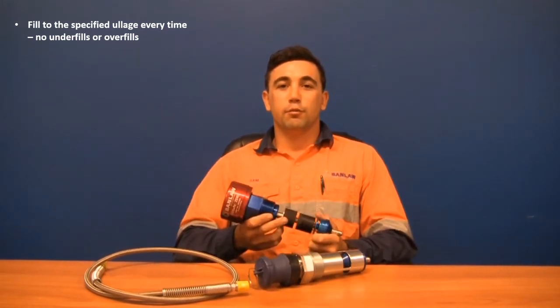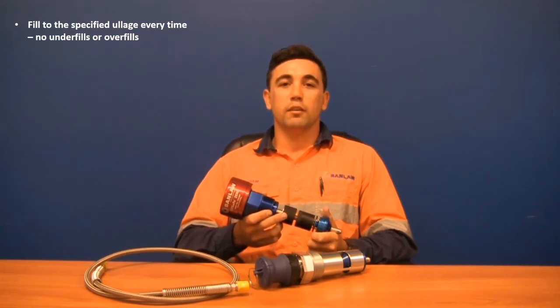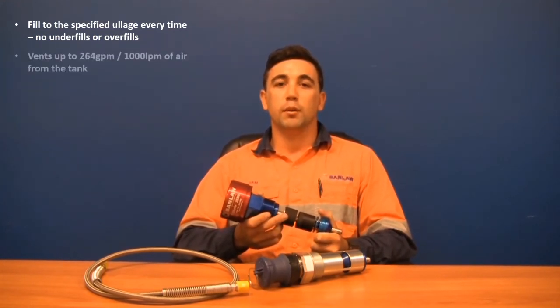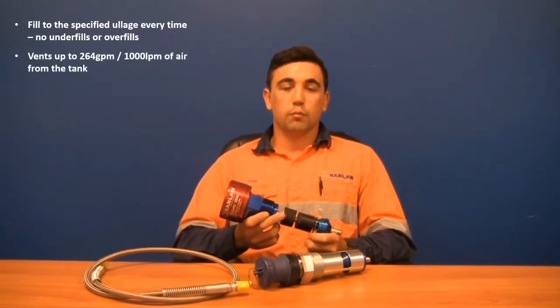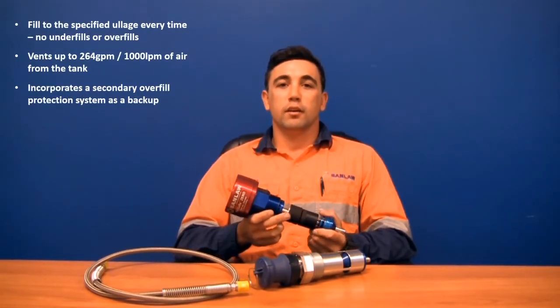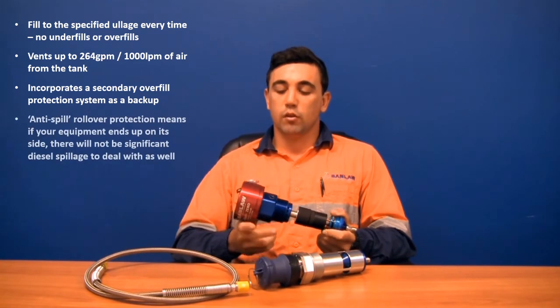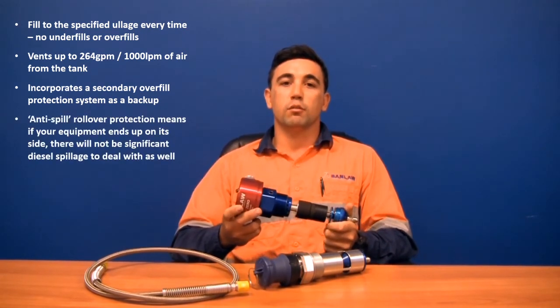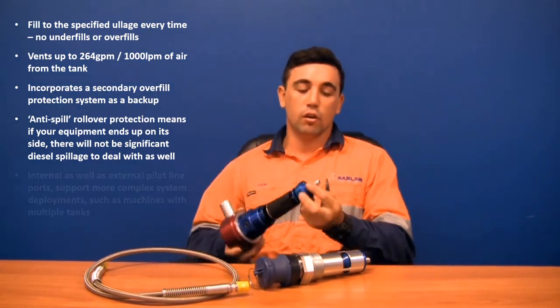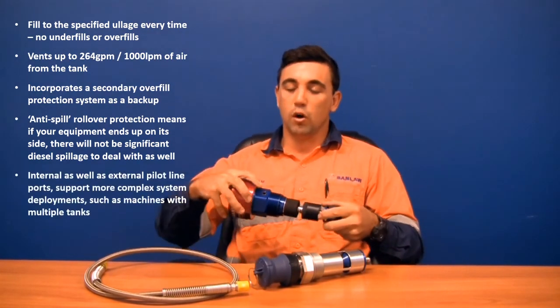A few quick features of the venting level sensor: it is accurate within a couple of millimetres of the designated shutoff level. It can exhaust air at up to 1,000 litres a minute or 264 gallons per minute. It has both a primary and secondary shutoff, and incorporates a rollover anti-spill device and a safety pressure relief. This venting level sensor can be used with both an internal and an external pilot line port.